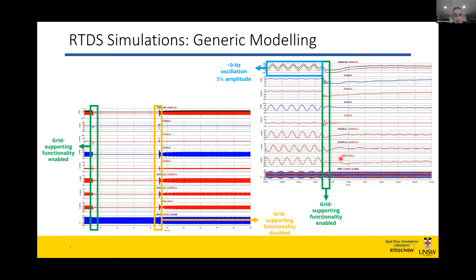And these slides really show that process that we demonstrated using the real-time digital system and the simulation and the modeling capability that gives you. And we could then show how different levels of inertia and damping could operate this system stably, and primarily show that without installing the battery energy storage system with the grid forming capability, without that, then you'd still be having these oscillations.